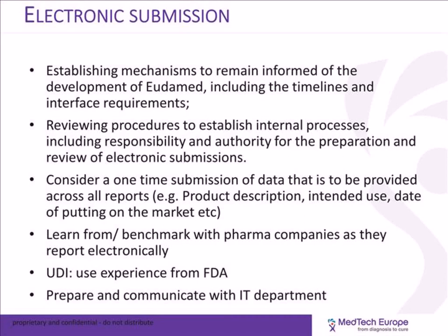It comes to an end with the date of application, which will be in May 2020. Now, there is an extension during which a product approved under the old regime, MDD, can carry on being placed on the market for a further 4 years, but this product needs to fulfill some requirements.